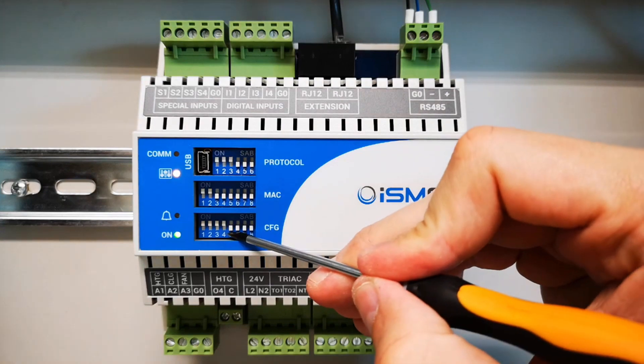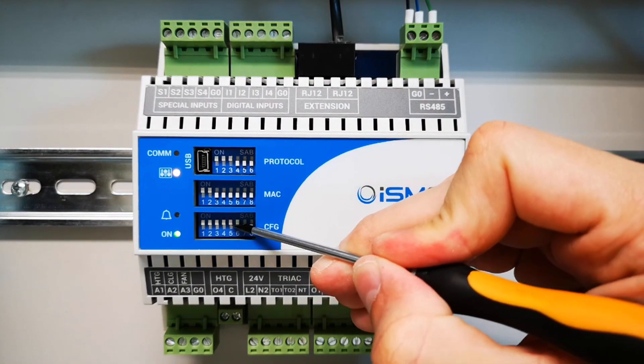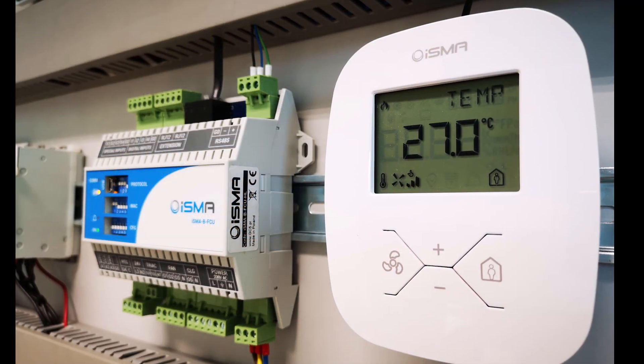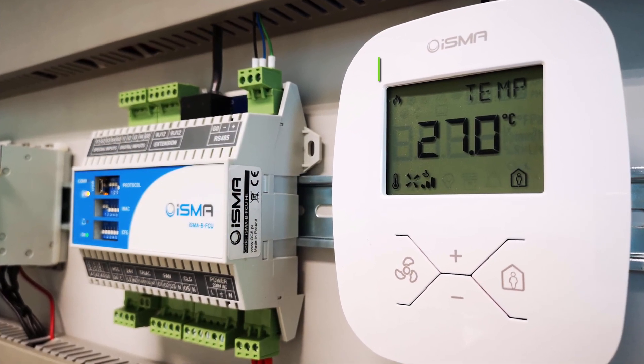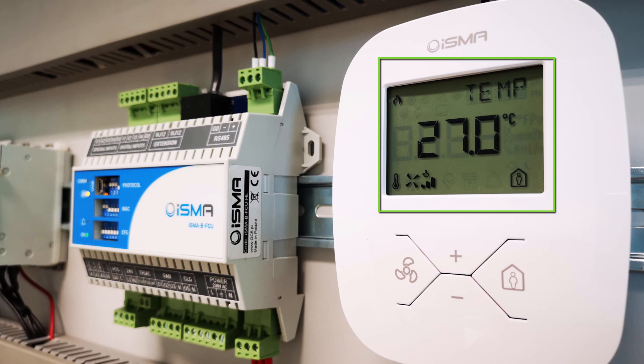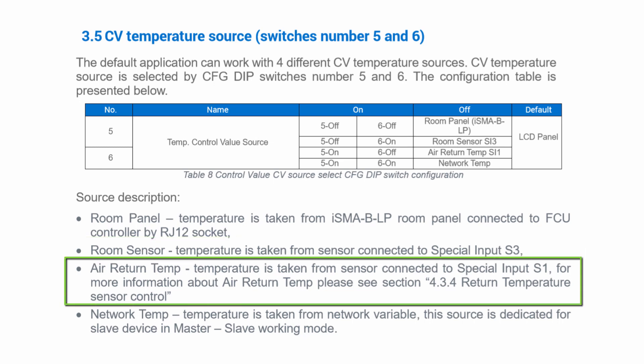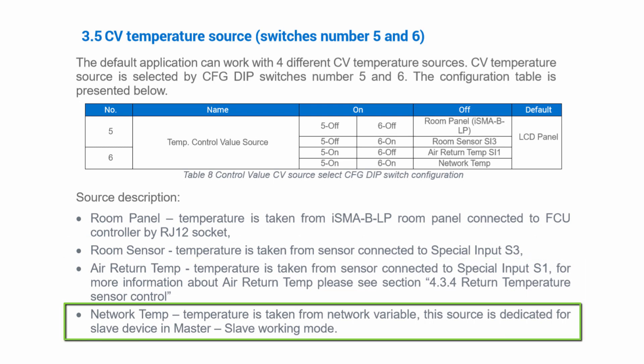The combination of the 5th and 6th DIP switches decides where the temperature control value will be taken from. There are 4 options: by default it will be the temperature sensor inside our iSMA-B-LP panel connected to the iSMA-B-FCU; other options are a room temperature sensor connected to special input number 3, a return air temperature sensor connected to special input number 1, or from a network variable.